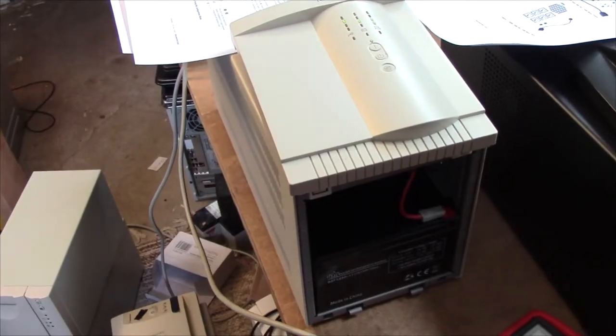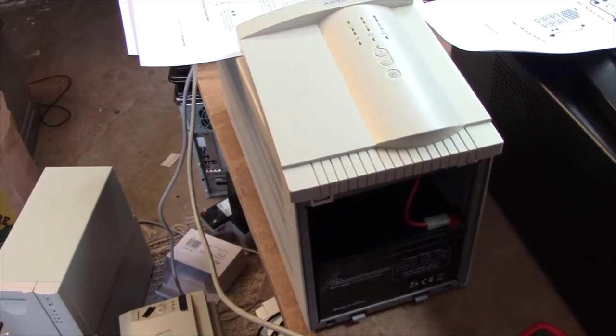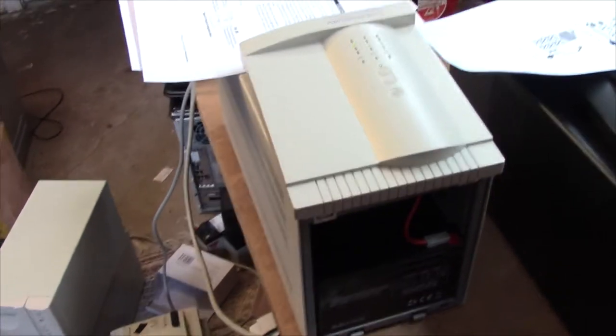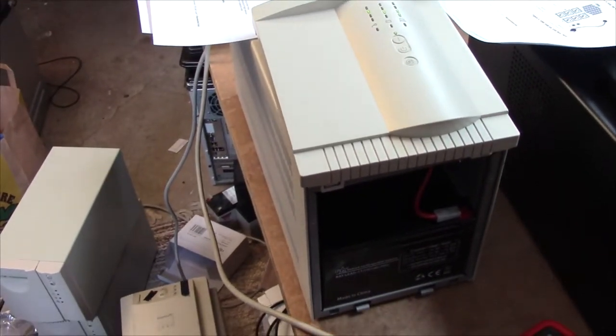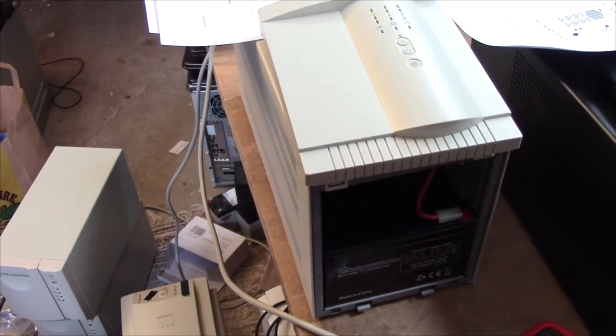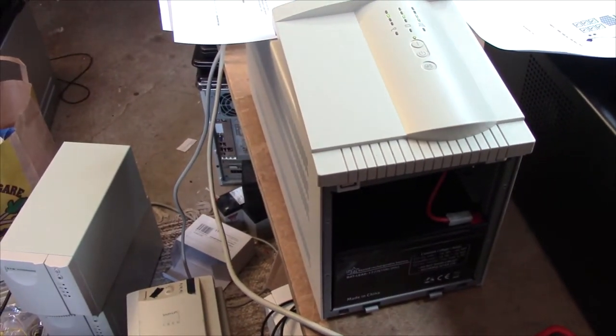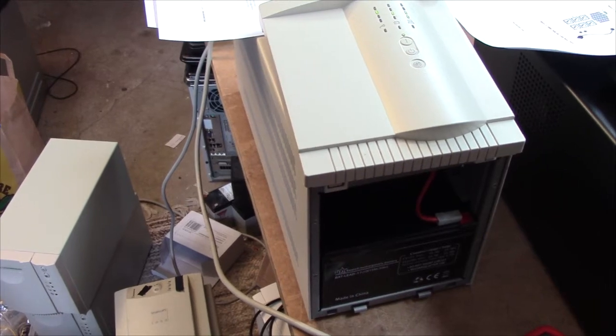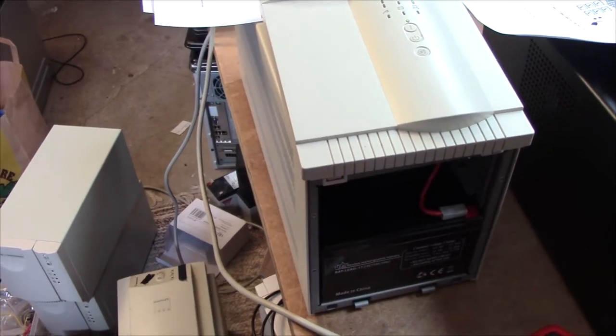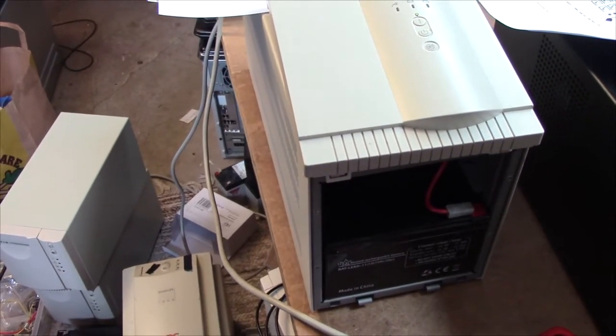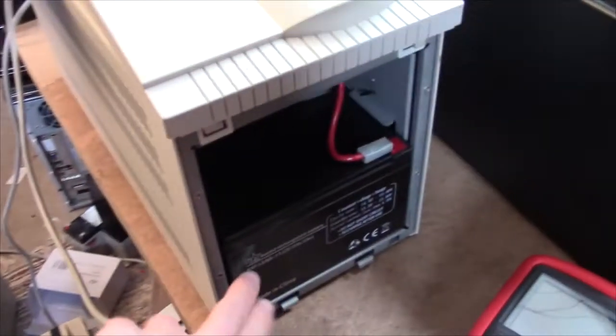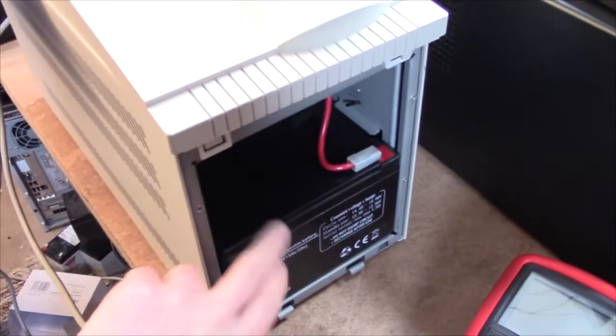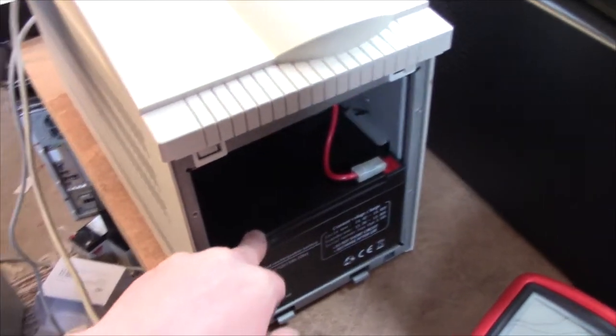The real downside to this unit is that it's got a stupid battery charger like an APC. It just floats the batteries. And I don't know how you change the voltage on it. It's set to float at about 13.75 volts per battery, which is too high.